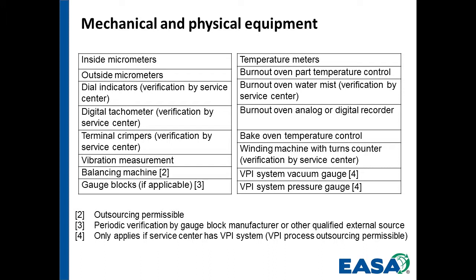If you have gauge blocks, these gauge blocks that we're speaking of here are the devices that are used. If you internally calibrate micrometers, you would calibrate those outside micrometers using gauge blocks, and those would go back to the manufacturer, to somebody that can certify them every 3 years. It's not an annual calibration. Just as a point of reference, calibration is required every year for anything that's in the program, the exception being the gauge blocks, which are every 3 years.